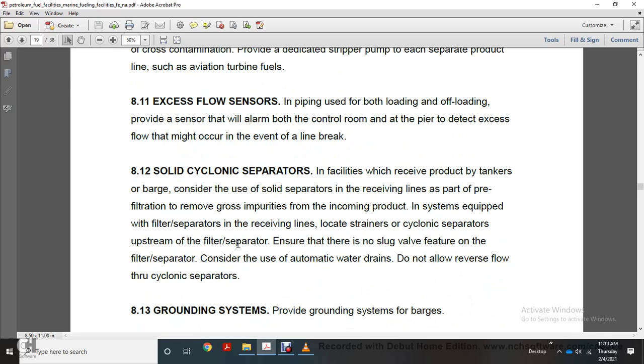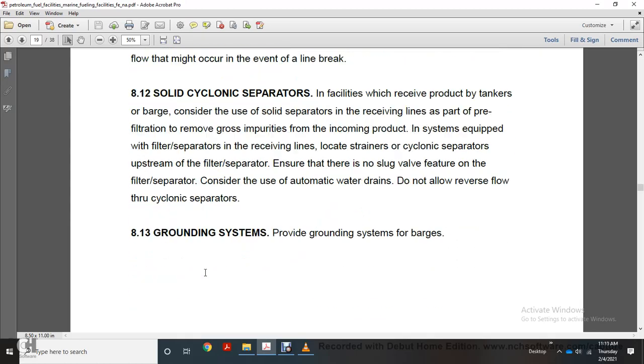Solid cyclonic separators. In facilities where product is received from tanker barges, consider the solid separator on the receiving lines upstream of filtration. Remove the gross impurities from the incoming product. The inside system equipment of filter separators, receiving lines, and local strainers includes cyclonic separators upstream of the filter and separator. Ensure that there is no slug valve feature on the filter separator. Consider the use of automatic water drains. Do not allow reverse flow through these cyclonic separators.